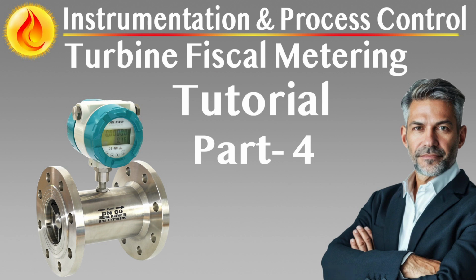Each turbine meter and associated meter tube must be inspected prior to assembly to verify compliance with dimensional tolerances and installation geometry. This includes upstream and downstream pipe lengths, the placement of flow straighteners, and positioning of temperature and pressure tappings. Turbine meters must be accompanied by a calibration certificate issued by an accredited facility.